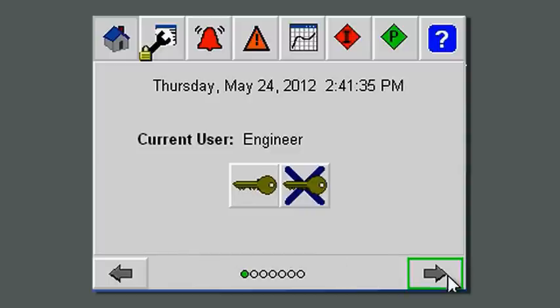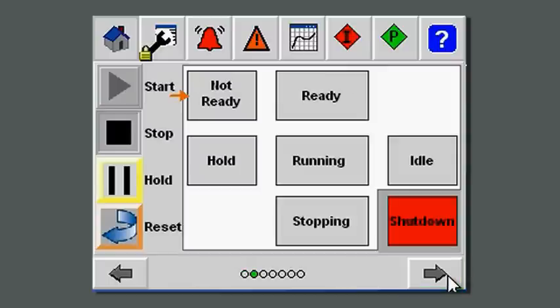As we move through the operating screens, you'll see the startup sequence display. This shows you exactly where you're at in the startup sequence. So if you start the steam turbine and there's a difficulty — either with an interlock, a permissive, or a trip — this screen will show you exactly where you're at, and it will also give you information on exactly where you need to go to clear the problem. This screen gives the operator a great deal of information about current operations.